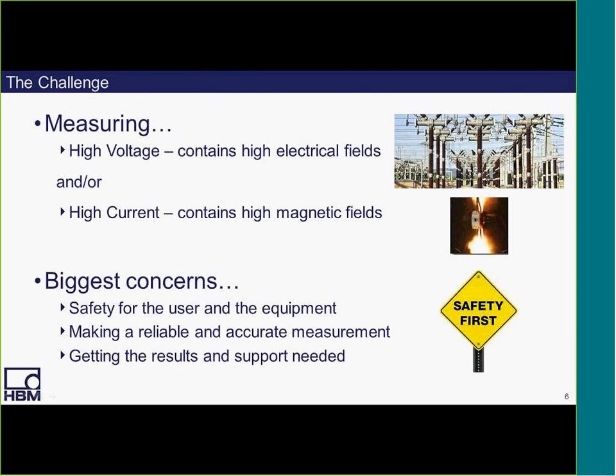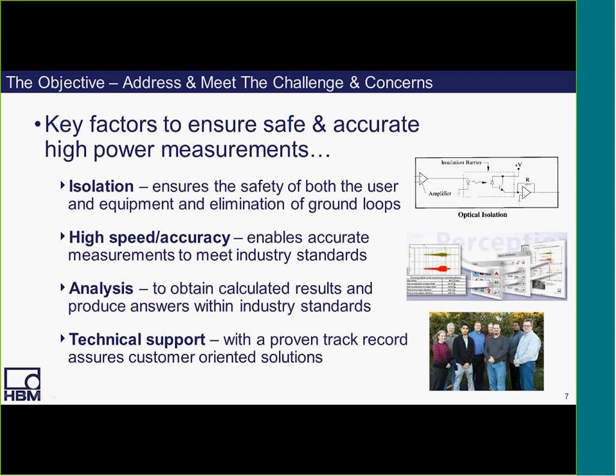Now, all the high-power applications we just mentioned have a unique and common challenge, and that is measuring high voltage, which contains high electrical fields, and/or high current, which contains high magnetic fields. Our biggest concerns in this type of environment are safety for the user and the equipment, making a reliable and accurate measurement, and getting the results and support needed. So our objective in this webinar is to address and meet these challenges and concerns by identifying and explaining these key factors that will ensure a safe and accurate high power measurement. These include isolation, high speed, accuracy, analysis, and technical support.